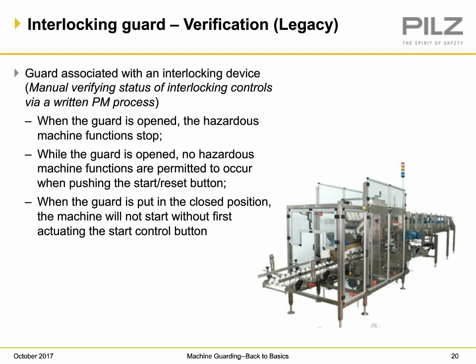When the guard is open, hazardous machine function stops. Okay, good with that. While the guard is open, no hazardous machine functions are permitted to occur when I push the start button or the reset button. Guard's open, I can push the buttons all day, nothing's going to move. When I shut the door, the machine will not start automatically without first actuating the start control button. So these are three steps that I have recommended to clients when they want to do some verification checking on legacy equipment that are interlocked but may not have the safety integrity that they're looking for.